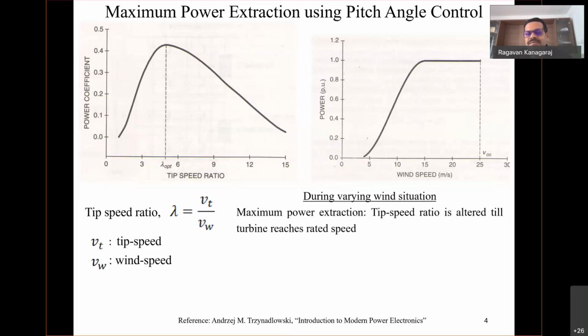Anji: so it's because of the rating of the machine we have reached. You are great. So we have the generator, we have already put a generator. That generator is rated for this much megawatt or mega volt ampere, whatever it may be. So we have already put the generator, thinking that 15 meter per second is the highest wind speed we will get in that terrain. But if we suddenly get 20 meter per second, we cannot change the generator again, do you follow? So corresponding to 15 meter per second, that system will give 10 MVA output.